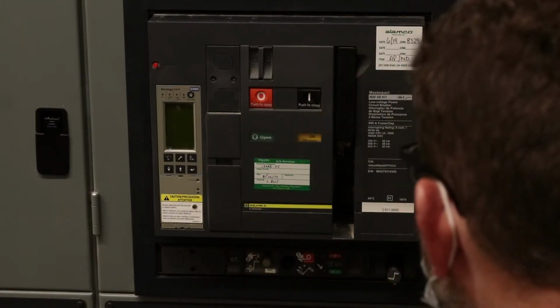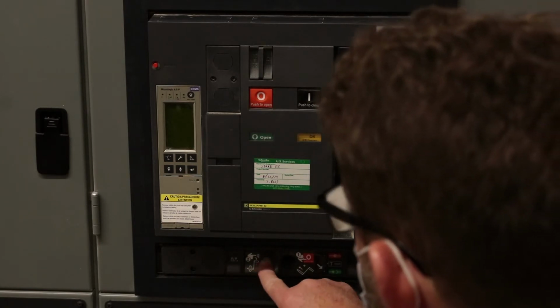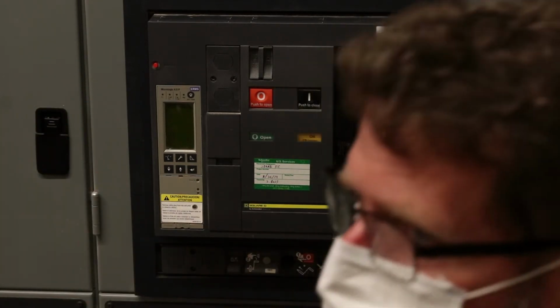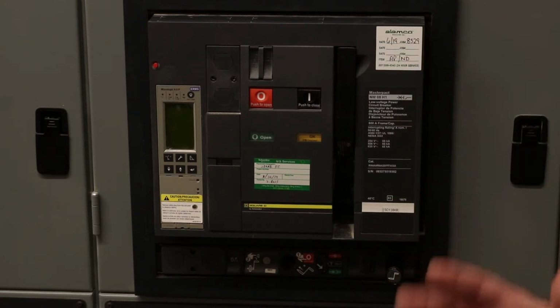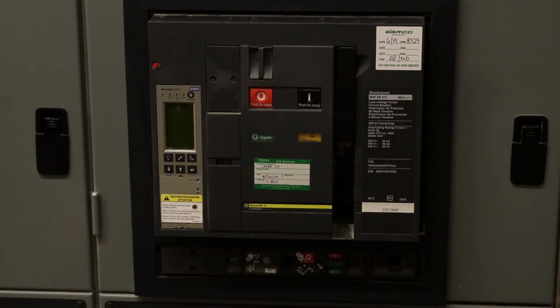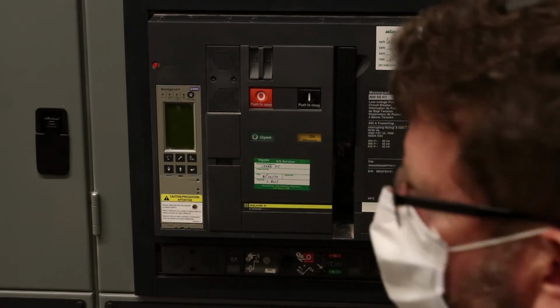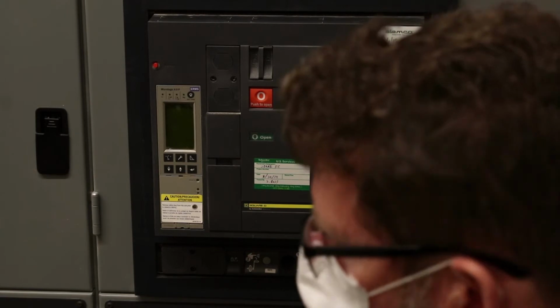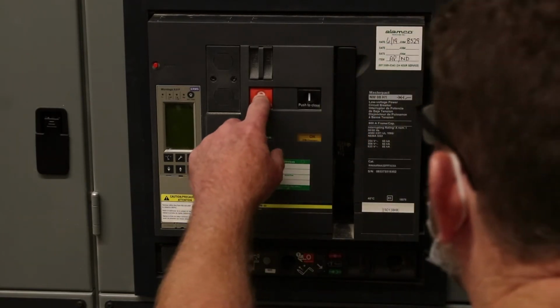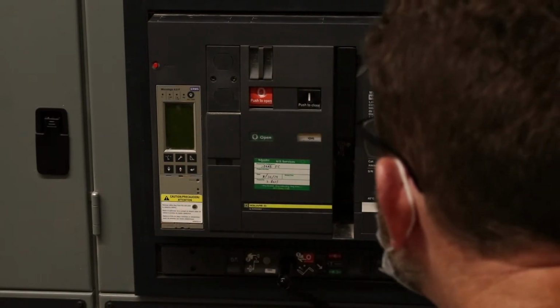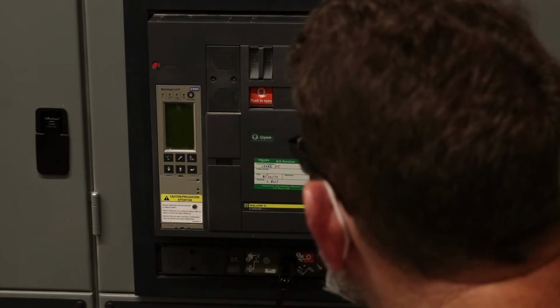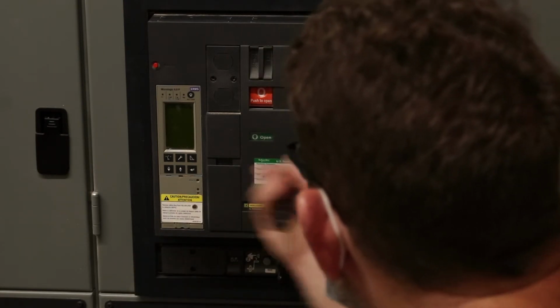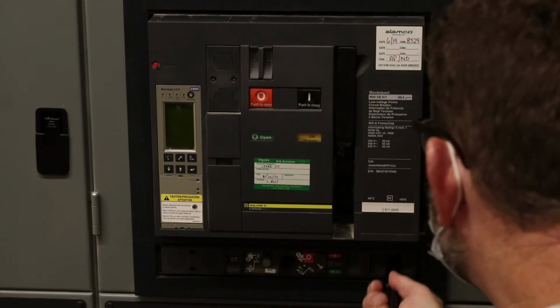Gray button. Yeah, gray button. If you walk in and you see one of these breakers with the button popped in, that's not a problem. The breaker's not going to vibrate out of the cell. It's just going to sit there. Some people will do that because they get all excited. They rack the breaker in to the test position, push the gray button, rack the breaker in to the connected position, and push the gray button again. That's not a problem. If you wanted to reset it, all you'd have to do is just come out of position a little bit and reset it.